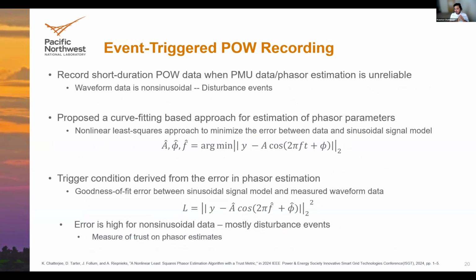So what we do is use a phasor estimation algorithm. Any off-the-shelf curve fitting based approach works fine here. We mention one particular approach, but others are just as good. Once we have those estimates of the phasor amplitude, phase, and frequency, you try to get this goodness of fit error between what your measurements are and what your estimated model is saying. If your actual data is a sinusoid and what you're trying to estimate is also a sinusoid, you would get a low error on this measure.